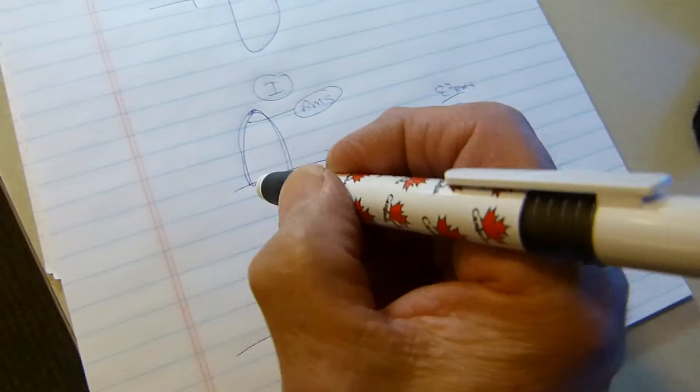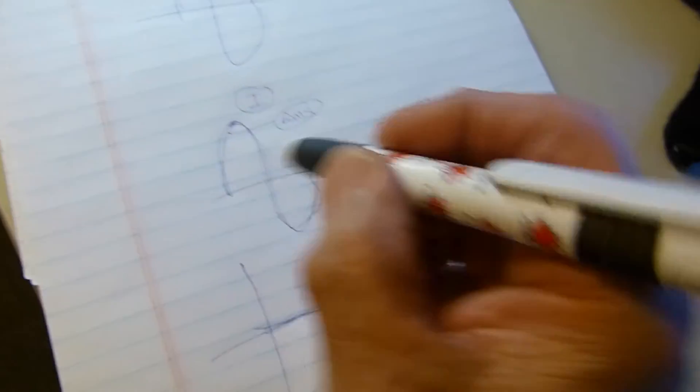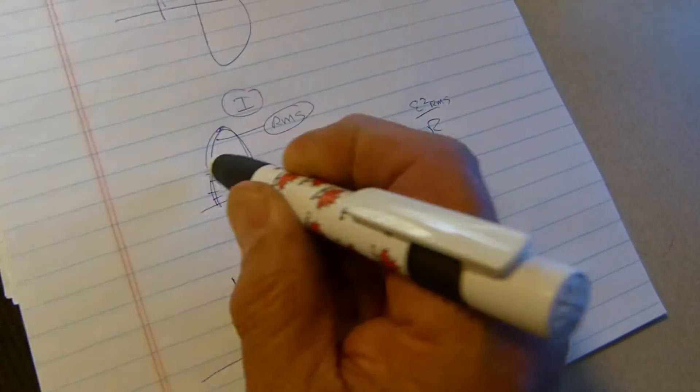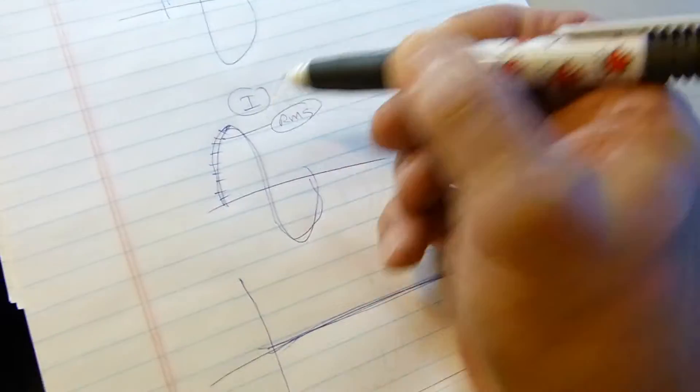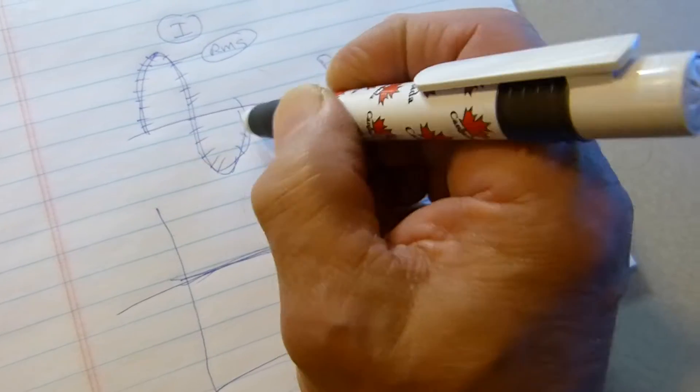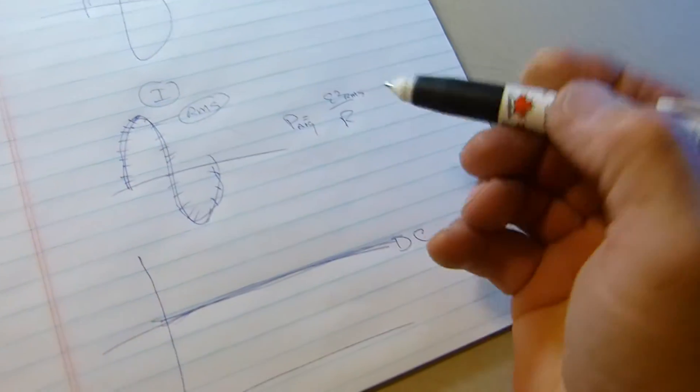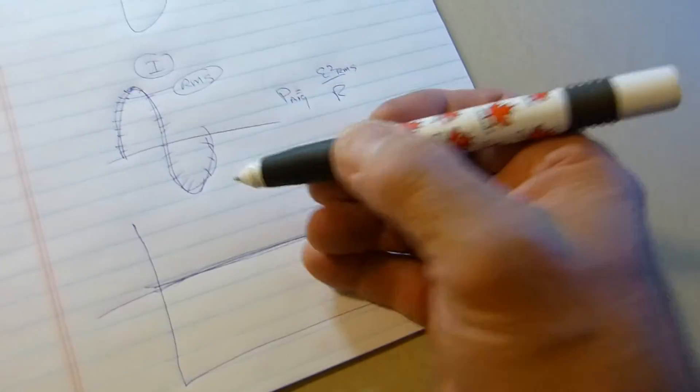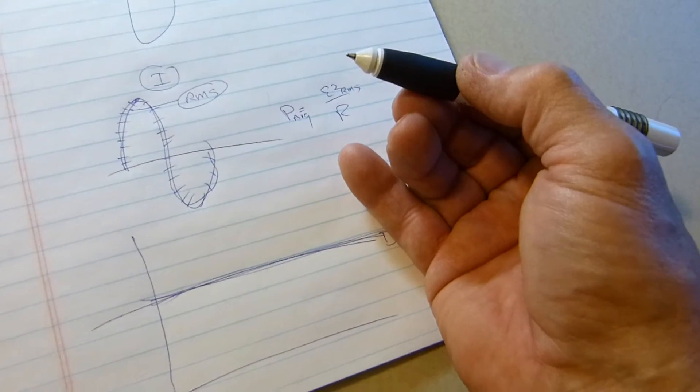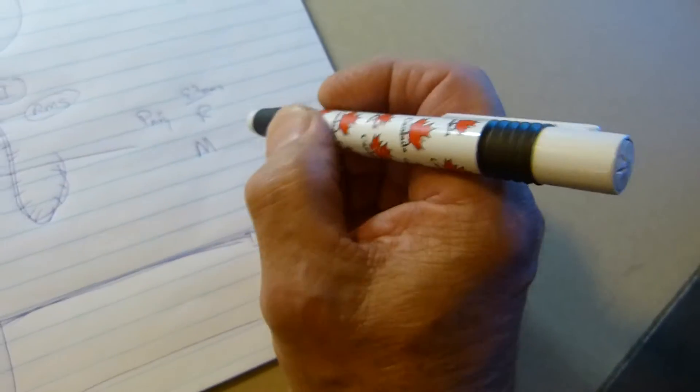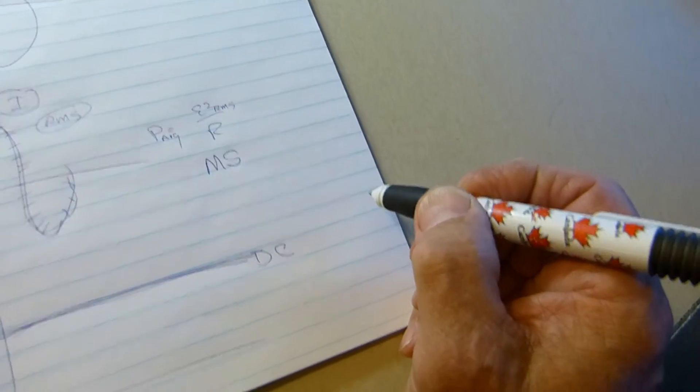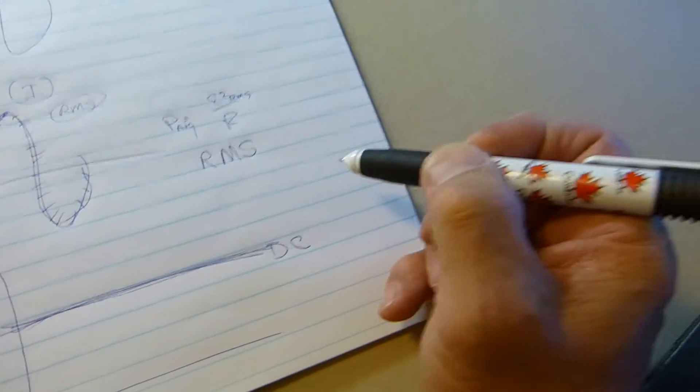What we do when we measure RMS voltage or current is we're making thousands of measurements of points all along the sine wave. We make all these measurements, square that number, add them all together, and divide by the number of points. Then we have the mean of the squares. If we take the square root of that, we get the root mean square value.